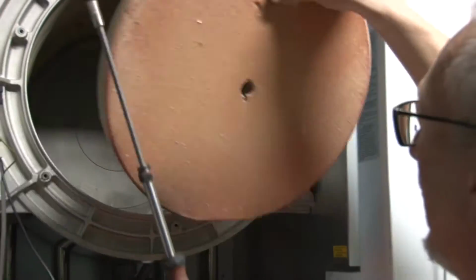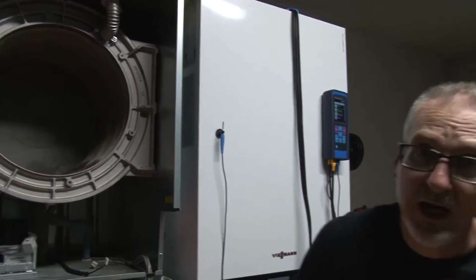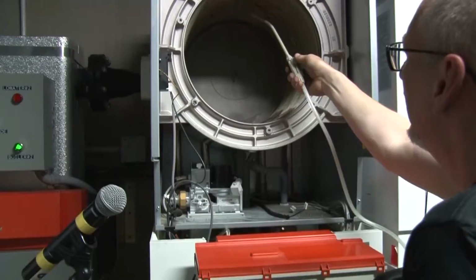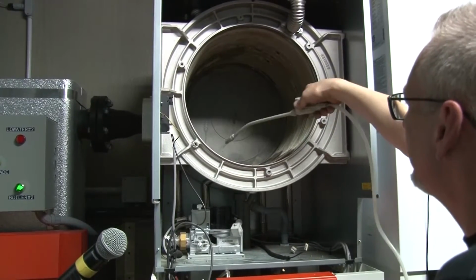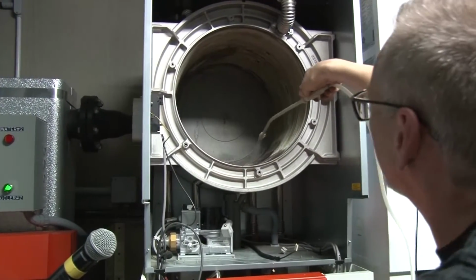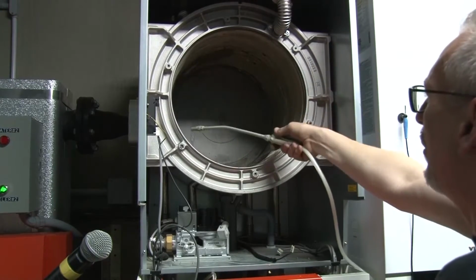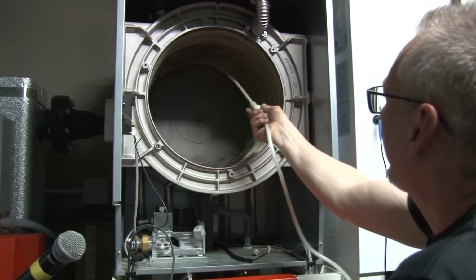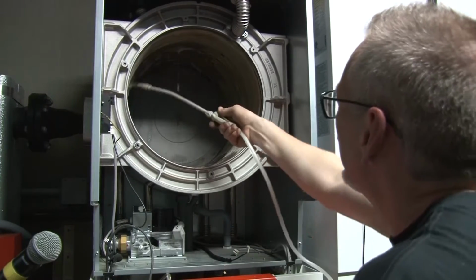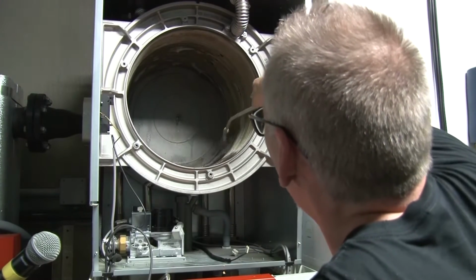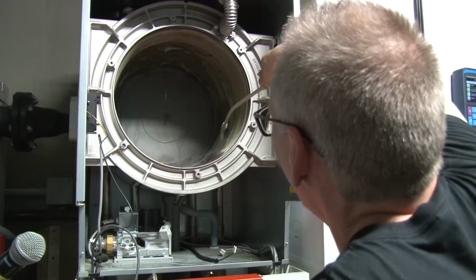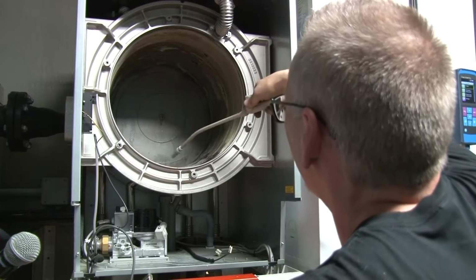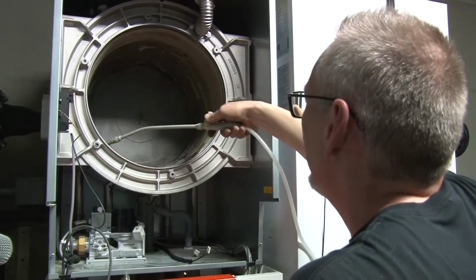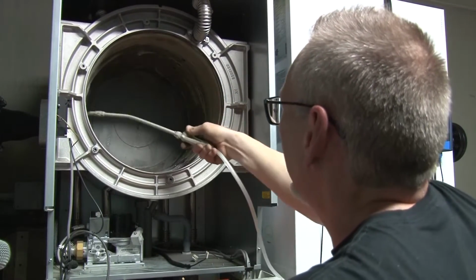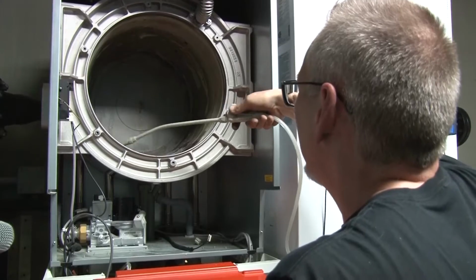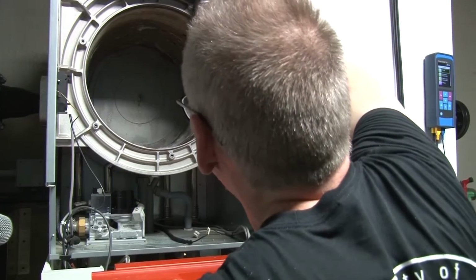There we go. And then we make sure we put this in a very safe place so it doesn't fall. This is a little pressure washer kind of thing you would use to basically spray your plants and stuff. It's a great little controlled flow of the chemical. Anytime I use chemical though, I'm going to make sure that I get in here afterwards and flush all this chemical out of the boiler. I do not want to have this chemical inside this boiler. Doesn't matter what kind of chemical it is. Unless it's water, you want to make sure you flush that out when you're doing your washing.